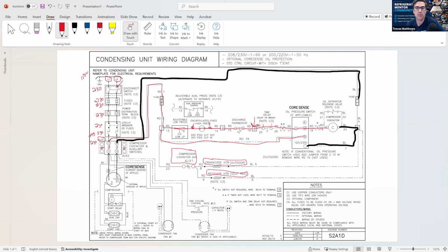So it's so important to make sure that you check this. I apologize, that would be 230. That would be 230 going through that high pressure switch. Okay. Using the meter going across the loads, especially with 230 volt, is so important. I know lots of, like I used to do it. I used to take it and I would go, L1 to ground. Oh, I got 115. I go L1 to ground, 115.